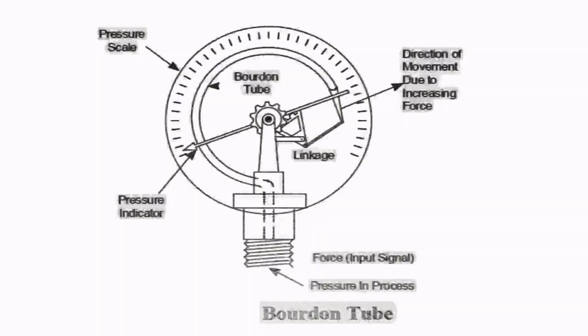Looking at the Bourdon tube — it was invented by Eugen Bourdon, a French watchmaker and engineer. It is a C-type gauge. The pressure goes inside the C-type Bourdon tube, and it has a link mechanism that connects between the C-type Bourdon and a quadrant-pinion arrangement, which moves to and fro. This quadrant-pinion arrangement is connected to a pointer that moves across the dial gauge.